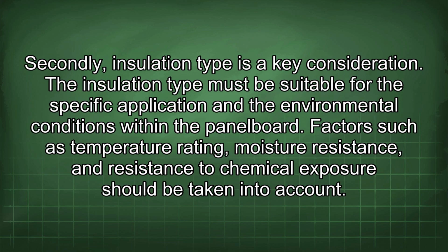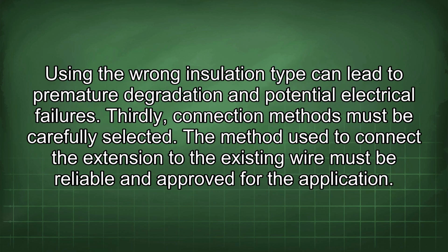Secondly, insulation type is a key consideration. The insulation type must be suitable for the specific application and the environmental conditions within the panel board. Factors such as temperature rating, moisture resistance, and resistance to chemical exposure should be taken into account. Using the wrong insulation type can lead to premature degradation and potential electrical failures.